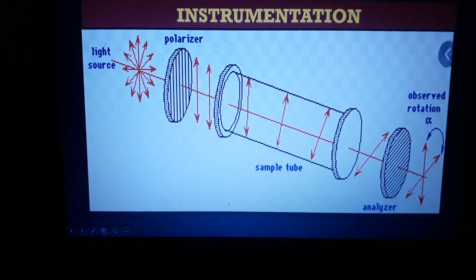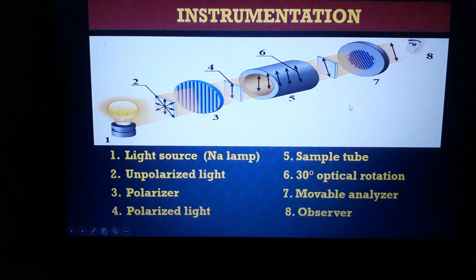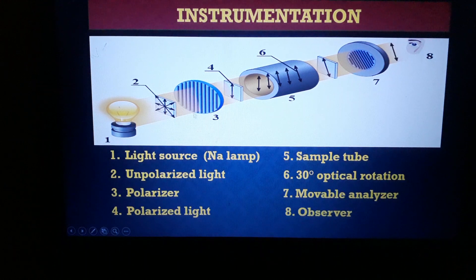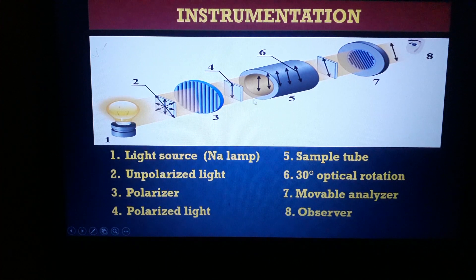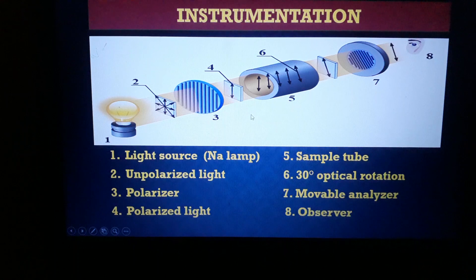The rotation caused by the sample can be measured as an angle using an analyzer — either left-side or right-side rotation. As shown in the diagram: unpolarized light enters the polarizer, becomes a single plane of polarized light, then passes through the sample solution containing the optically active substance, which rotates the plane of light left or right, and the analyzer measures the angle of rotation.